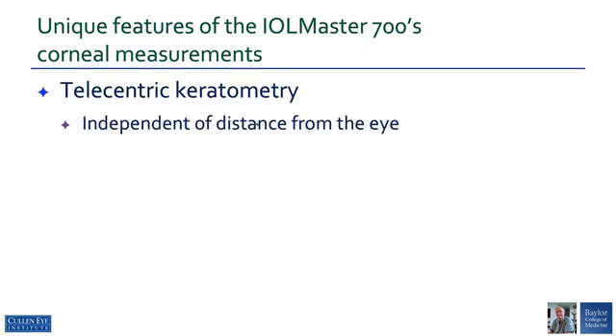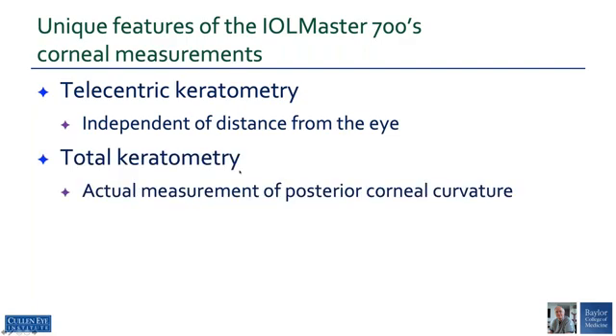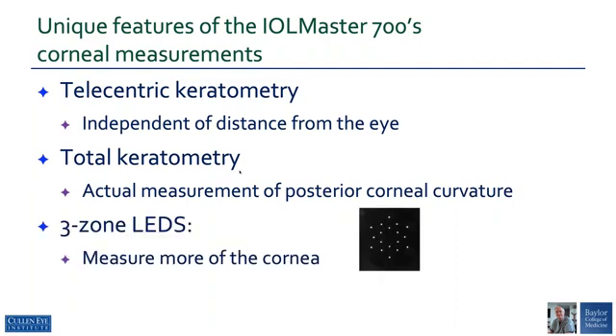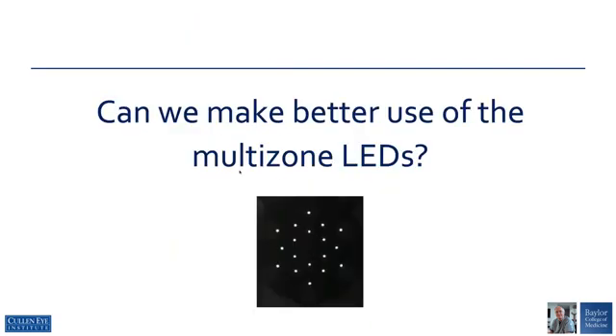The IOLMaster 700 has three very unique features for its corneal measurements. The first is telecentric keratometry, in which corneal measurements are made independent of the distance from the eye. The second is total keratometry, which provides actual true measurement of the posterior corneal curvature with the swept-source OCT. The third is the use of three-zone LEDs that enable the device to measure more of the cornea, which raises the question: can we make better use of these multi-zone LEDs?